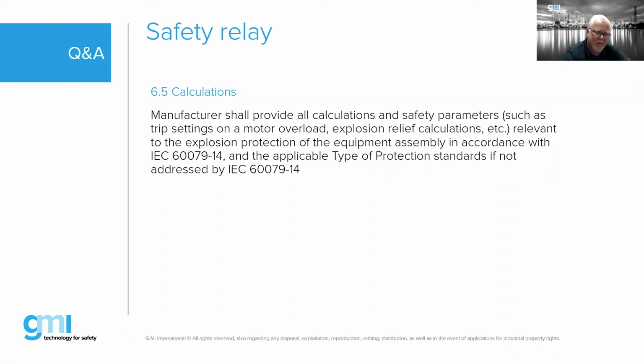Where this -46 really comes from is, say, we have an EX motor and some sort of overload protecting this EX motor. We're looking at it from an assembly standpoint, and we also have to take into account the installation requirements referenced in -14, like selection of cable type and all the interconnects. Where a safety relay comes into play, if we want to get this entire skid package certified under the -46 standard, then we would have to provide all those calculations, the safety parameters, all of that good stuff. That's spelled out in 6.5 in the -46 technical specification.